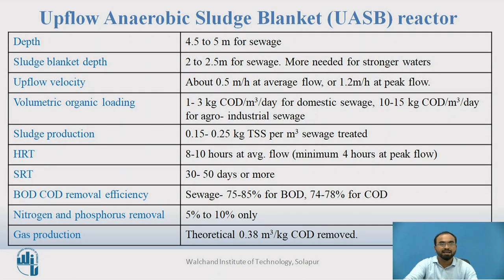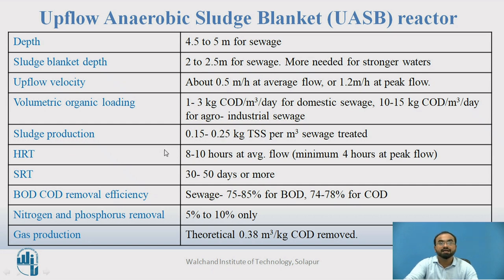Talking about its parameters: normally the depth of UASB is around 4.5 to 5 meters for sewage. The sludge blanket zone depth is around 2 to 2.5 meters for sewage, and can be increased for stronger wastewater. Upflow velocity is normally kept at about 0.5 meters per hour for average flow, and can be increased up to 1.2 meters per hour. The volumetric organic loading is typically 1 to 3 kg COD per cubic meter per day for domestic sewage, and 10 to 15 kg COD per cubic meter per day for agro-industrial sewage. Sludge production is generally around 0.15 to 0.25 kg TSS per cubic meter of sewage treated. HRT is typically kept around 8 to 10 hours for average flow, with a minimum of 4 hours for peak flow.